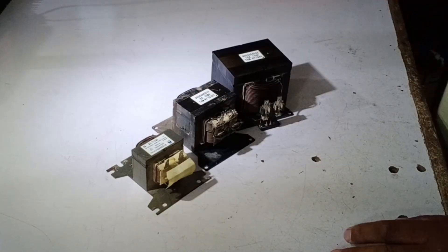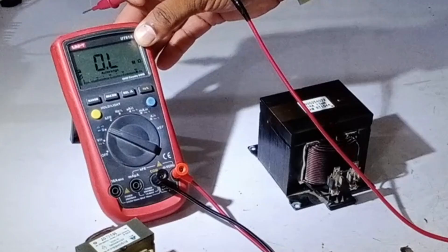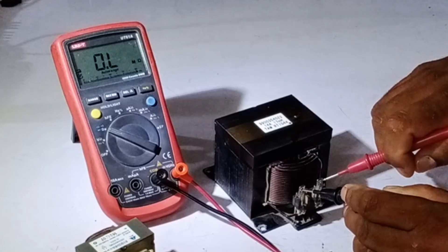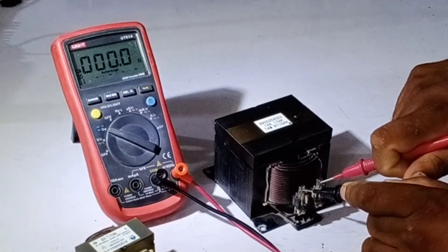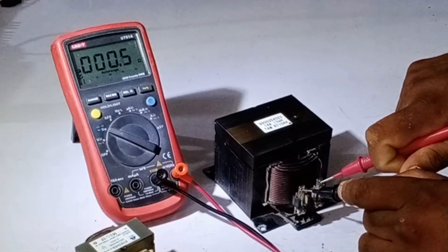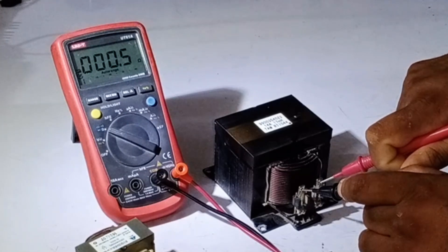Let me also explain the method to test it. You need to bring a multimeter and set it to the resistance mode. I will connect both probes of the multimeter to the terminals of the reactor. You can see that the multimeter shows a reading of 0.5 ohms. When the multimeter shows this value, it means that the reactor is perfectly fine and there is no issue with it.